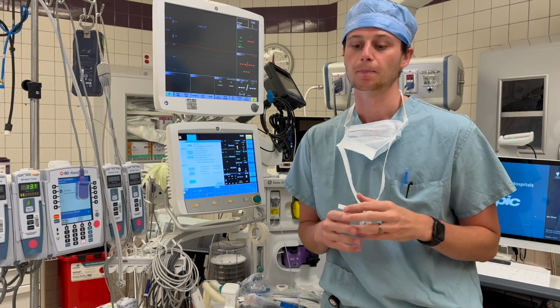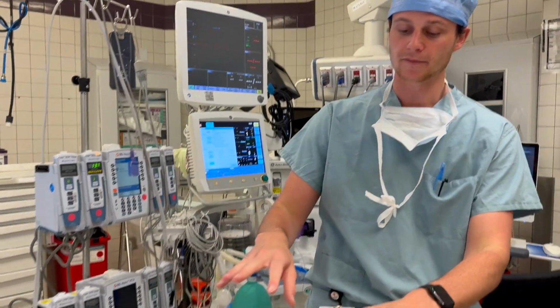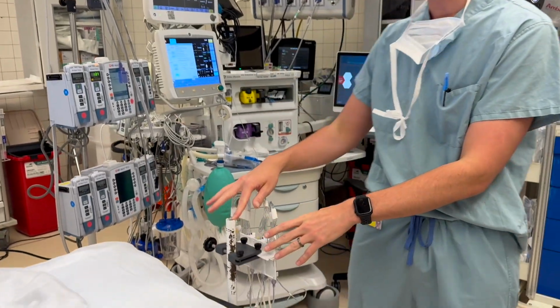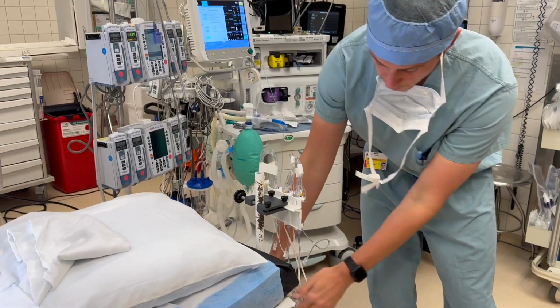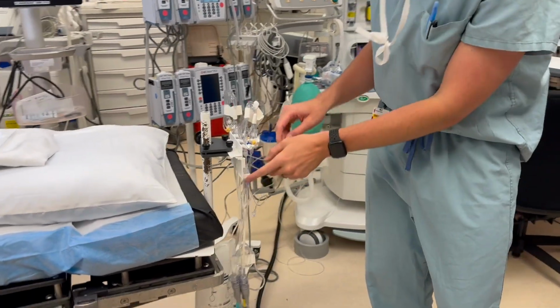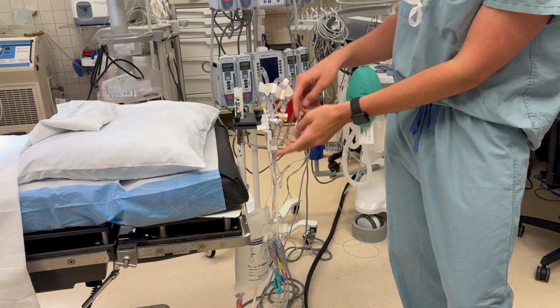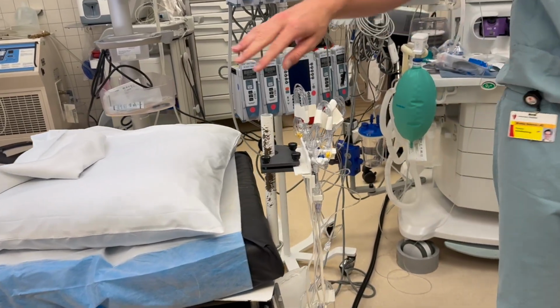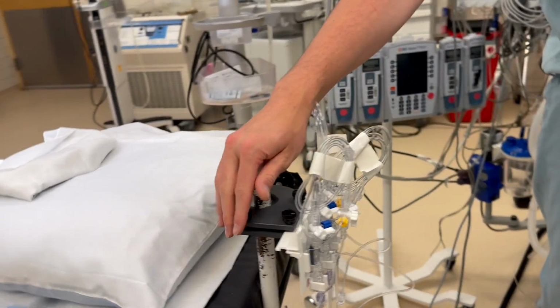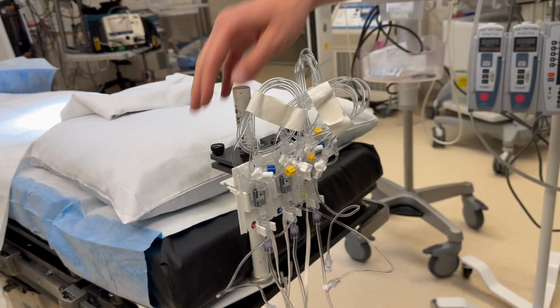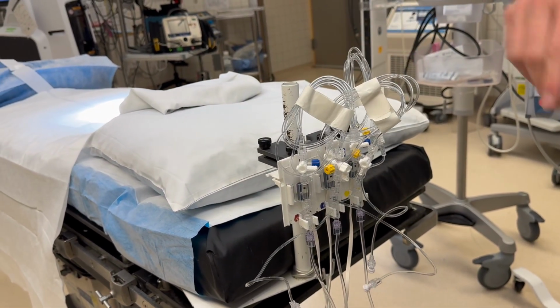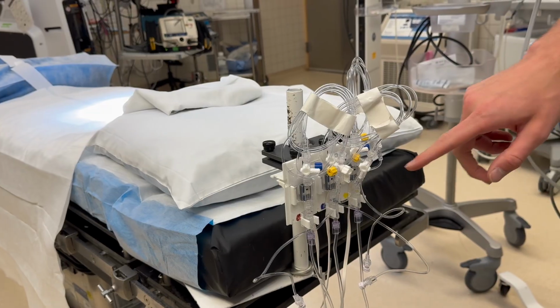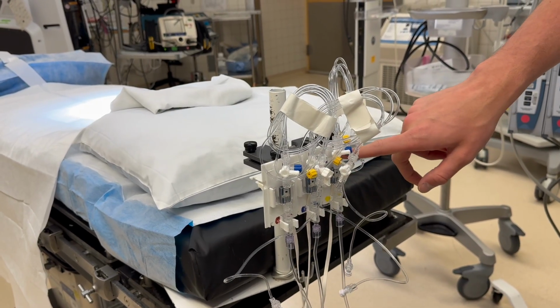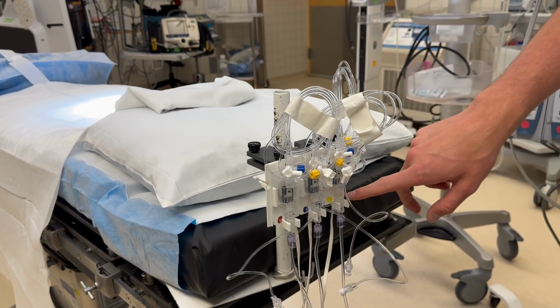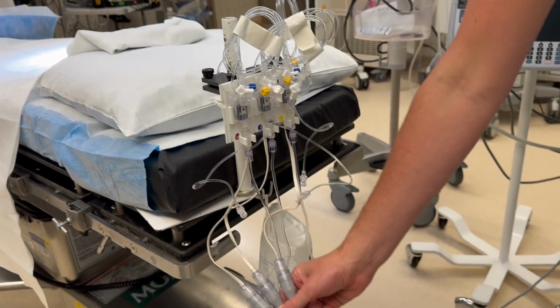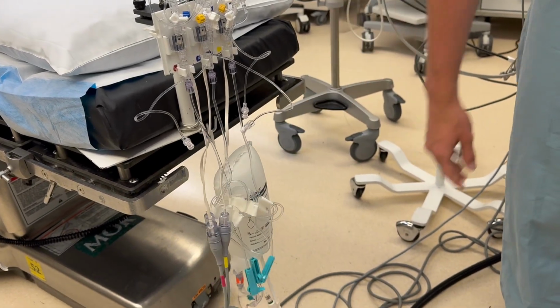We also additionally want to make sure we have our triple pressure bag set up and ready to go. These can be found in the workroom. They look similar to the pressure bag, except they have 3 of these transducers instead of the 1. We also have this very handy holder that is going to hold all 3 of our transducers. We have our arterial line transducer, our CVP transducer, and our pulmonary artery pressure transducer here, all 3 connected to our triple pressure cable.